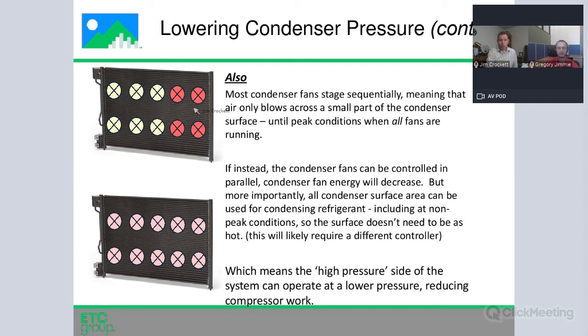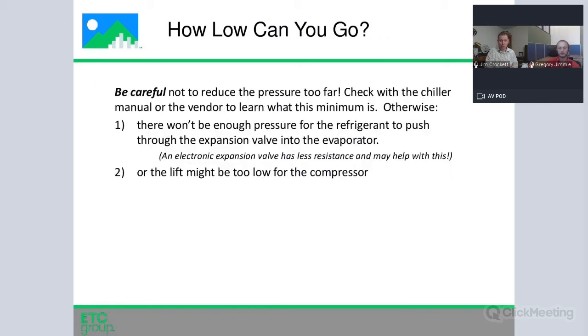If instead you can program your condenser to have all of the fans move in parallel, you win twice. Number one, your fan energy goes down thanks to the affinity laws. And second, your heat transfer at your condenser becomes much better, which means you can lower your temperature and you can lower your pressure. And this will generally require some sort of either a modification or an aftermarket type of controller, but it can result in substantial compressor savings.